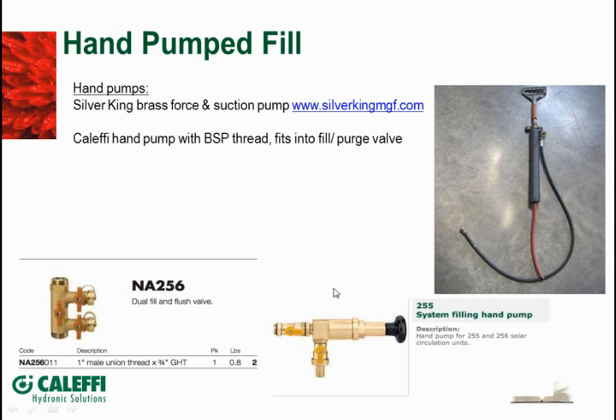What it's really handy for is if you're going to go to a job like you should every couple years on a solar system and take a little sample of the fluid out, take your tester with you, make sure the pH is good, check the freeze protection rate, take a sniff of it, make sure it isn't going bad and discoloring and stuff like that. Well, you've got to pump a little bit back in there if you take a cupful out, and that's what this is nice for. You can just, without having to take a motorized pump or a bucket or anything down with you, pump it right back out of the container that you sampled it with right back into the system.